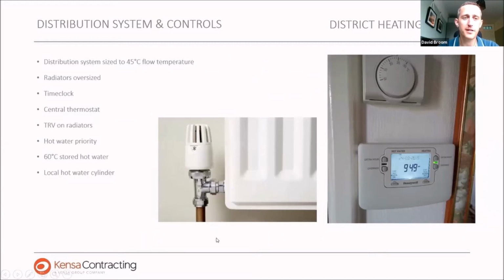So as far as the end user experience is concerned, you end up with a traditional wet heating system, so radiators with TRVs. The radiators will be sized around a 45 to 50 degree flow temperature. So what that means is we'll give the same amount of energy to the room as a radiator from a gas boiler, but we need to increase the surface area to compensate for the slightly lower flow temperature. So typically radiators for a ground source heat pump will be 2.4 times the size of a radiator used for a gas boiler.